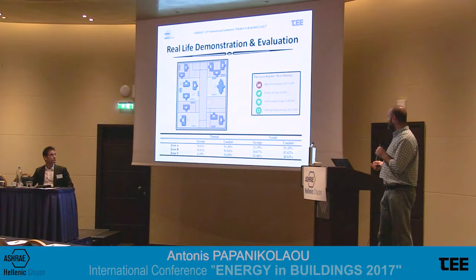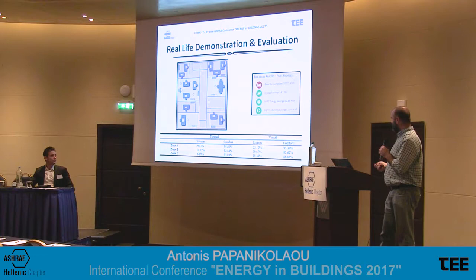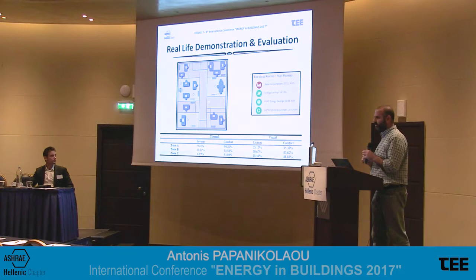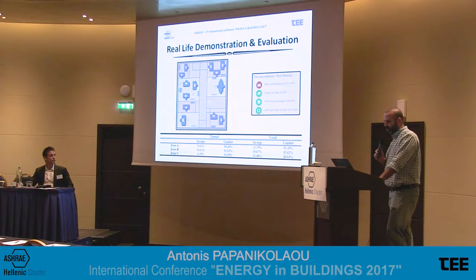The comfort level displayed corresponds to the profile model that we created in advance. Depending on the actual conditions, either enforced by the facility manager or by the facility itself, we can monitor how the people feel within the building in terms of thermal and visual comfort. We can see that we can keep comfort quite high with some not negligible savings in energy consumption in the HVAC system of the building. For visual comfort, the gains are actually much higher, even though the aggregate consumption of lights is lower than HVAC, mainly because of the inertia of people who don't tune the lights at the fine-grained level they would like.